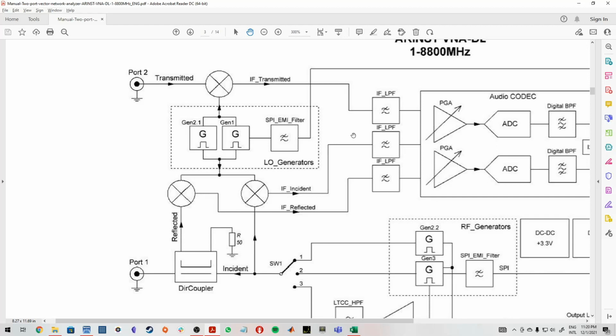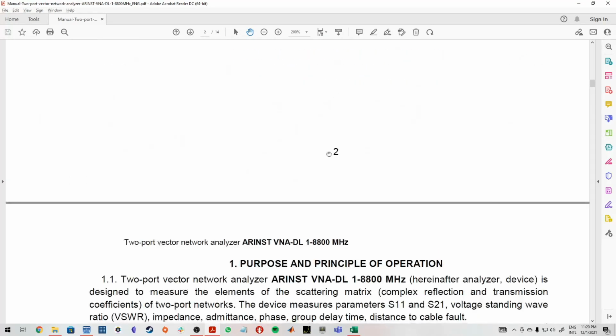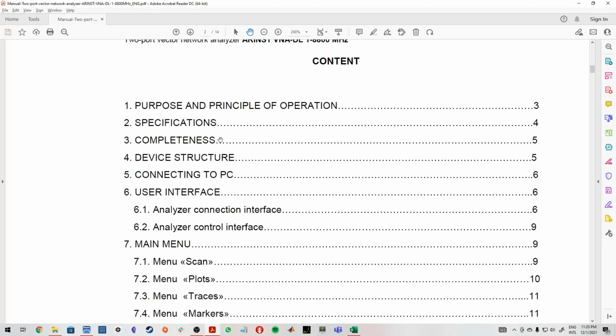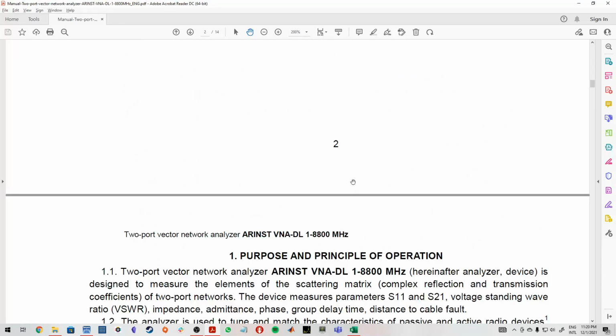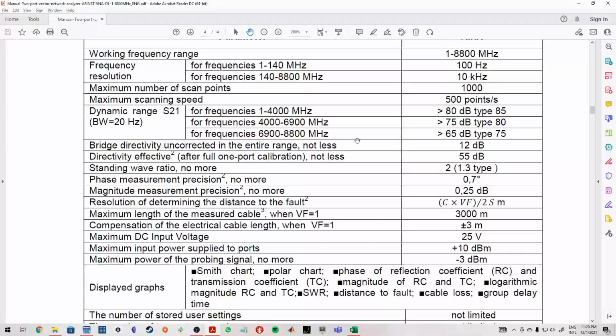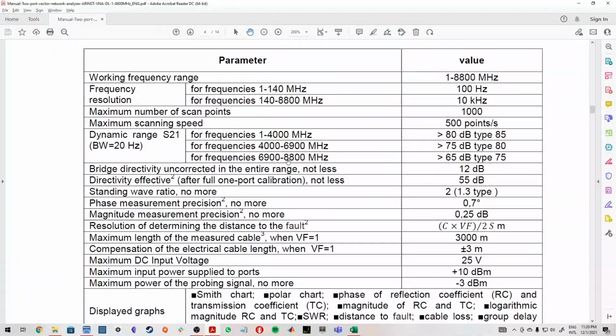This device achieves, if I'm not wrong, 70 dB of dynamic range in the higher frequencies, right? Maybe 60 at 8.8 gigahertz. I don't remember the specs well. We can check it right here. So let's see if there are specifications. It's right next. It's right here. So you can see, up to 8.8 gigahertz is better than 65 dB. This must be typical. Oh, typical 75.